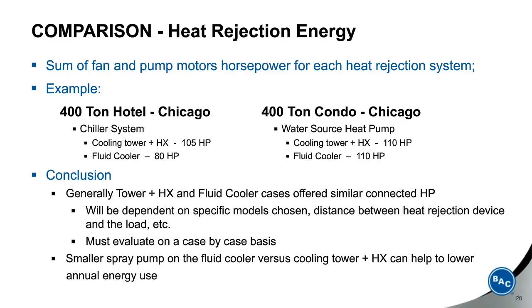Under what circumstances would a plate and frame heat exchanger be used with a chiller to cool the condenser? Generally, what I've found in my experience is there has to be a driver for that. One of the best examples early in my career was a chiller plant on an auto manufacturing factory, and it was located actually next to a cement plant. The cement dust was being drawn into the open cooling towers, and of course that cement dust then wound up in the chiller barrels and basically causing a very hard scale that was very tough to remove. The auto plant decided to take out the open circuit towers and replace those with fluid coolers, and that kept the cement dust out of the chiller barrels.